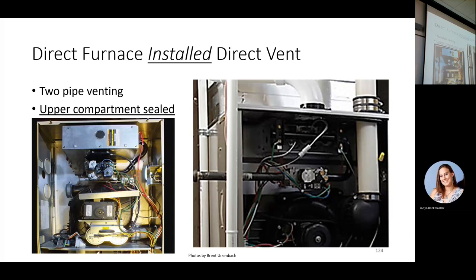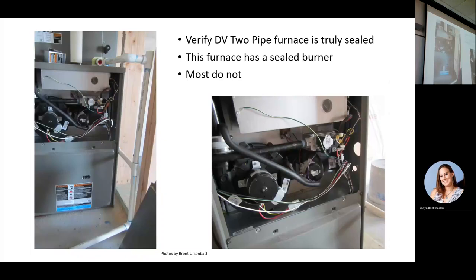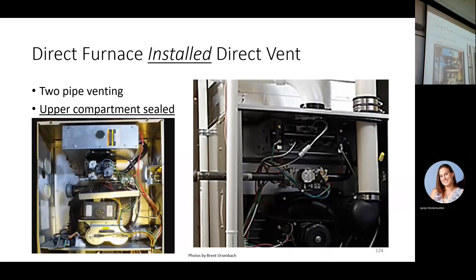So we have to make sure that if our furnace, and this is installation instructions, if the upper compartment does not have a sealed burner like this, and I know that's a little hard to see, but that's the burner manifold right there and the burner's going in. Here's our combustion air coming in, our vent going out. We have to have the grommet that comes through with the furnace on the gas line, and any knockouts or anything have to be sealed. Otherwise, it's not direct vent. It's not sealed combustion.